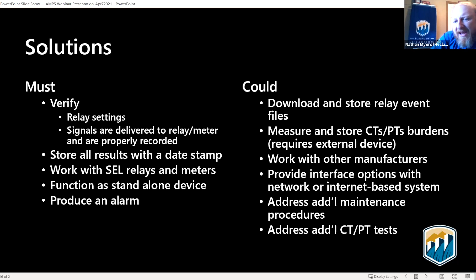So for example, we want to be able to communicate between relays to compare signals from different CTs and PTs located on the same bus. We also want to be able to communicate with microprocessor-based protective relays and power meters to ensure the signals going into the devices are similar. We would like to be able to query the relays to ensure that the proper settings are installed within the relays themselves. And we'd like to produce an alarm anytime we see an unexpected signal at the protective relays, power meters, etc.